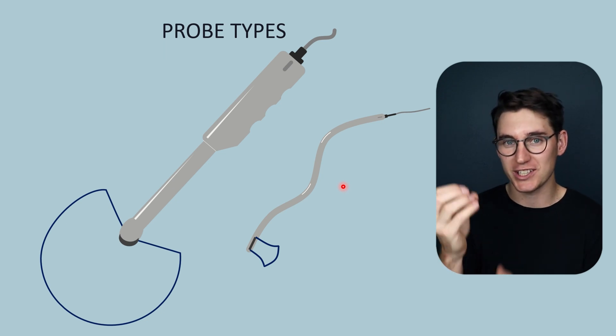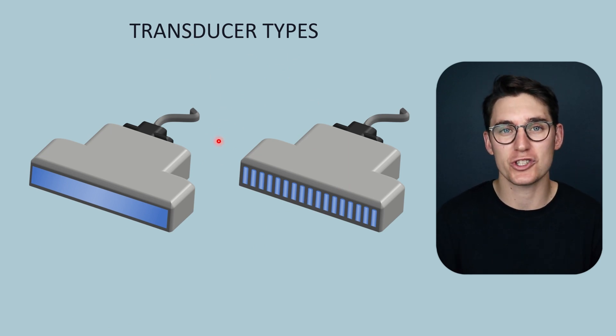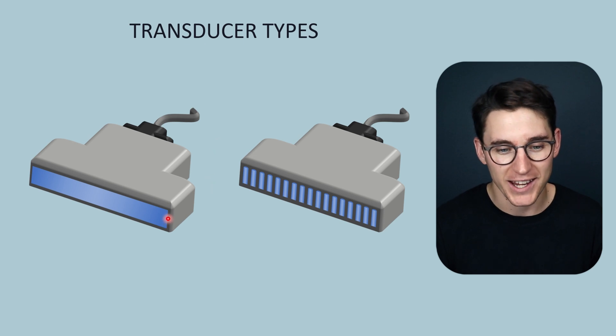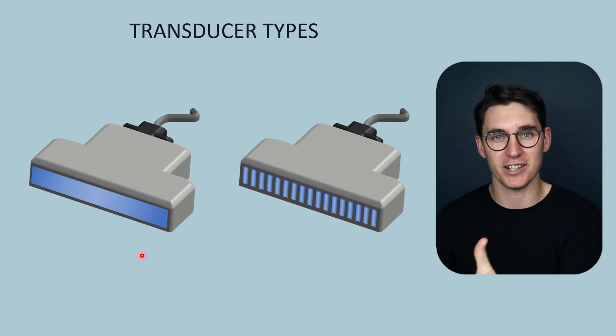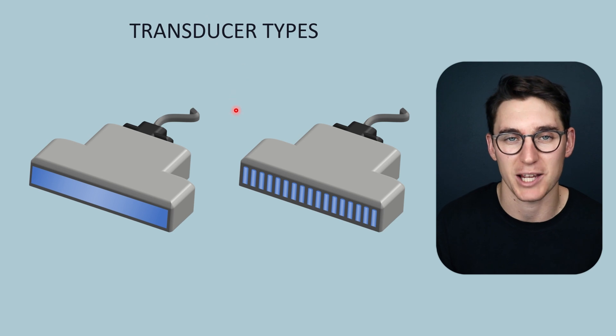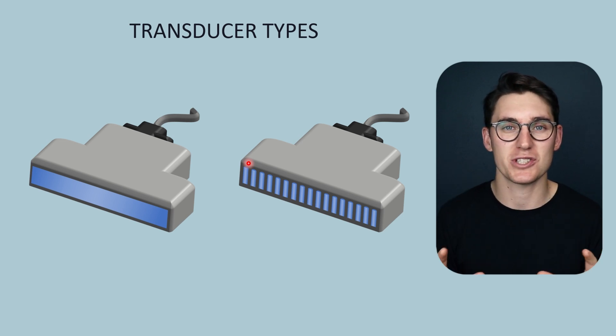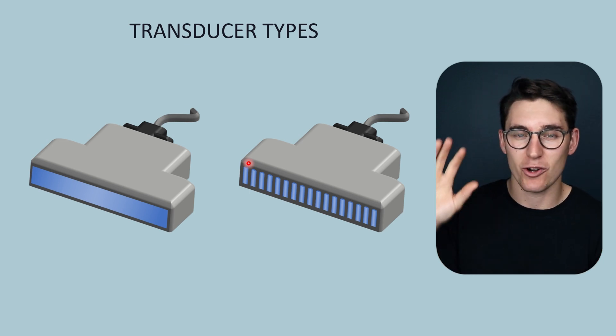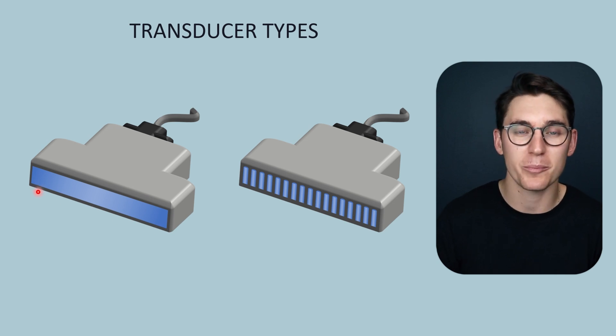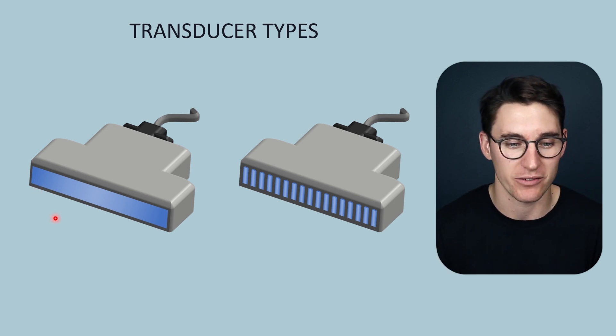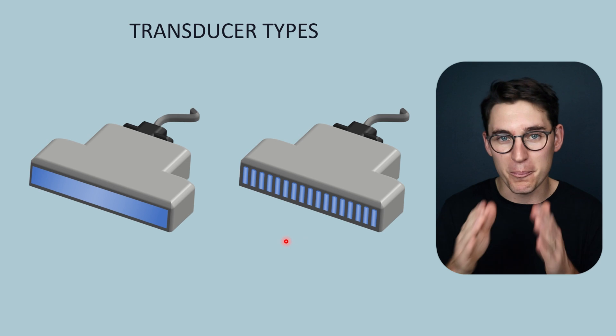Now we're going to look at the transducer types, which refers to how we go about creating our wave — generally referring to the crystals on the face of our transducers. Our linear and curvilinear transducers can have the same transducer type; it speaks to how we propagate that ultrasound wave. Broadly, we can separate transducer types into single element transducers and array transducers. Single element transducers have just one PZT crystal making the ultrasound wave, but in practice we've largely moved to multi-element array transducers.